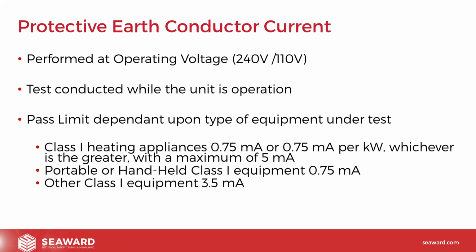As we hinted, when you're discussing insulation tests, it may be more applicable to perform the test whilst the unit is in operation. So this will generally mean that in the hire industry, we're either performing tests at 110 volt or 240 volt, dependent on the device and the test operating voltage.